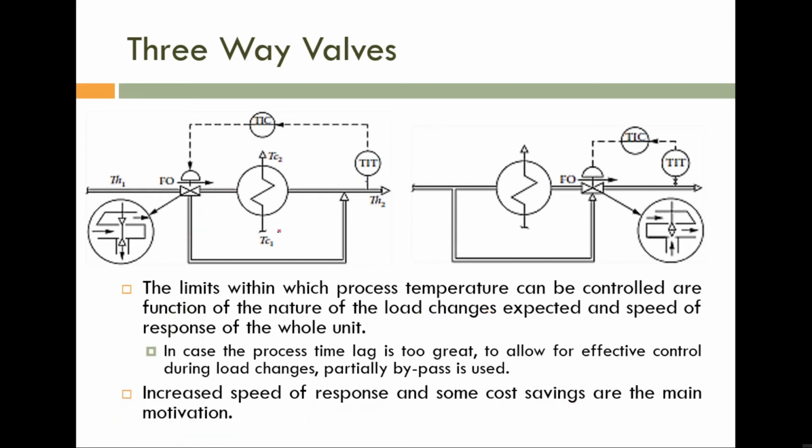You can see that the temperature is measured here. I told you we are discussing the cooler, so we want to maintain a low temperature here. So the temperature is measured. And here you can see that we are using a fail to open control valve towards this direction. So this direction is fail to open, which means this path is fail to close.